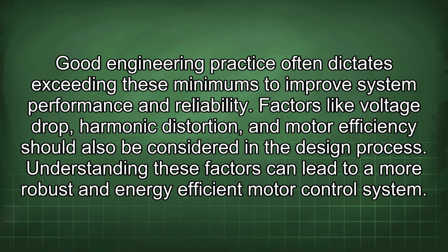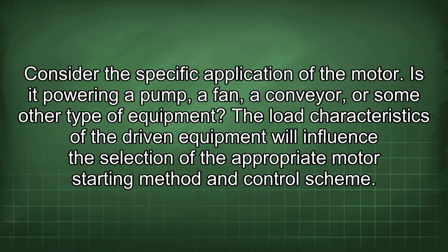Good engineering practice often dictates exceeding these minimums to improve system performance and reliability. Factors like voltage drop, harmonic distortion, and motor efficiency should also be considered in the design process. Understanding these factors can lead to a more robust and energy-efficient motor control system. Consider the specific application of the motor. Is it powering a pump, a fan, a conveyor, or some other type of equipment?